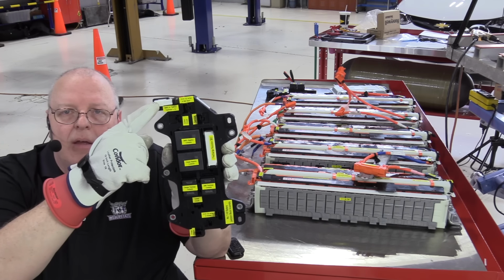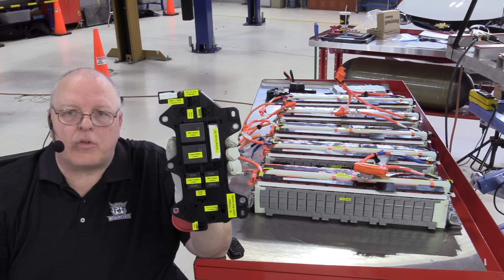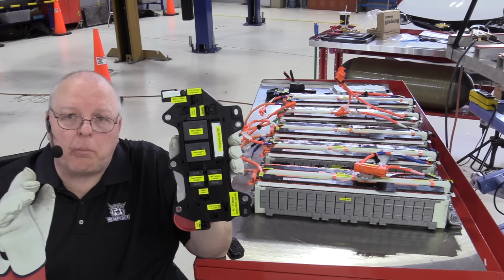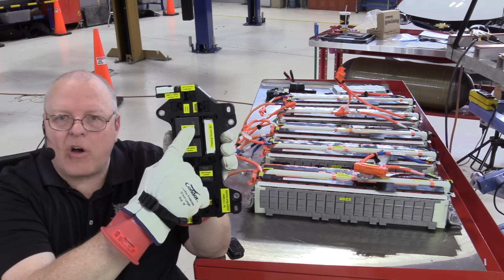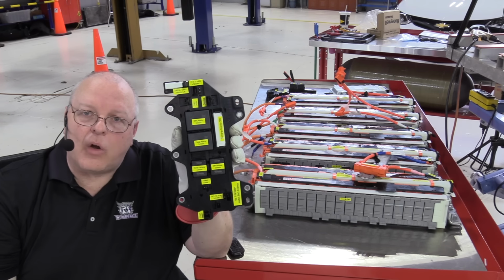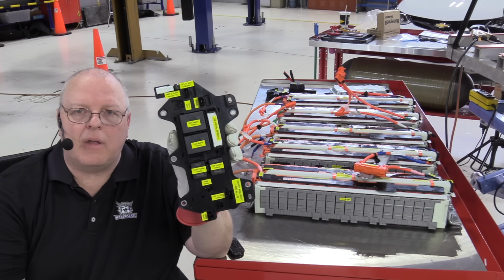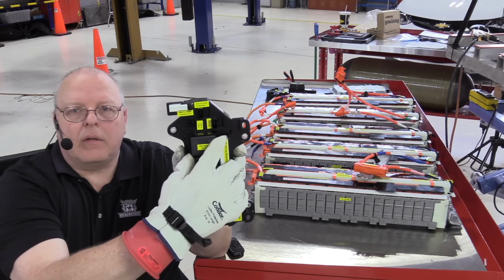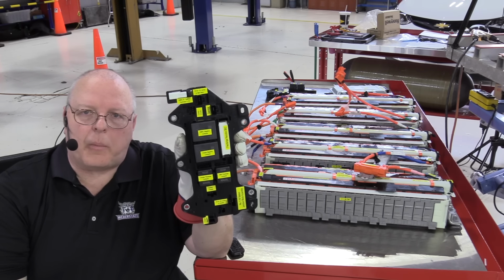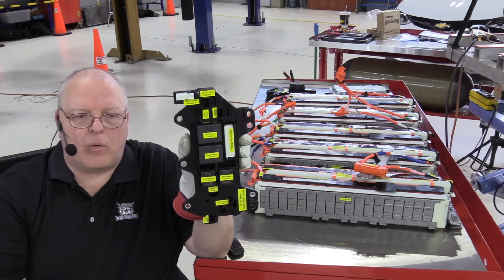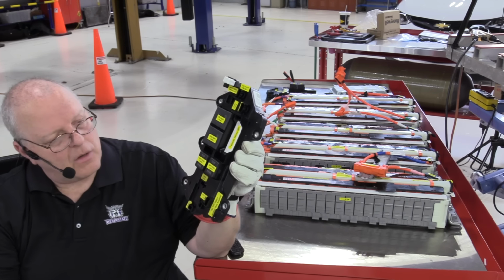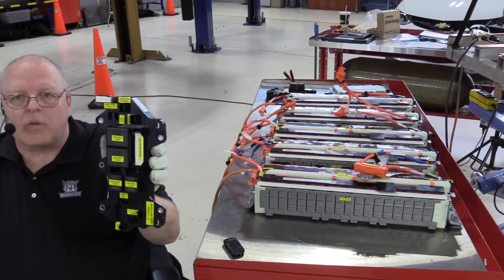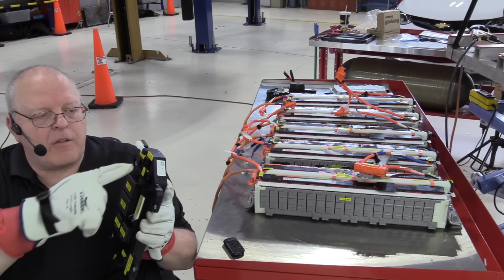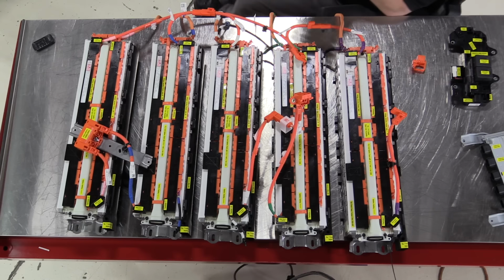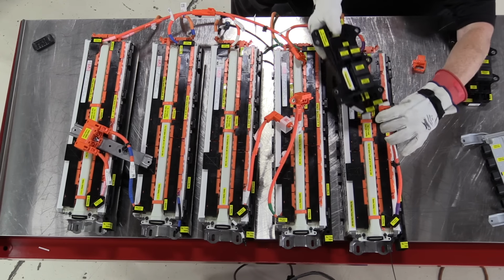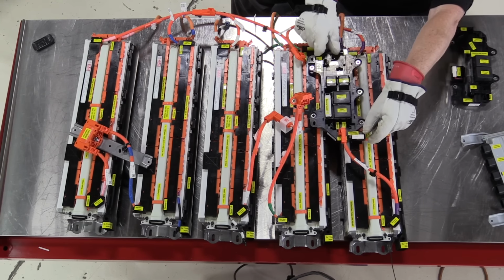By the way, this has an additional electrical connector here that connects to a thermistor to monitor the actual temperature of the physical blade, the terminal of the negative contactor, where the current from the battery goes into that contactor. They monitor the temperature of the contactor terminal to make sure it's not getting too hot. There's also a service port here where we can connect up a discharging machine to discharge the battery, or even to charge the battery with an external machine on the negative side, and there's one on the positive side as well. So this is where battery cell stack number 1's negative cable is going to attach. Right there. And then it just sits right there.